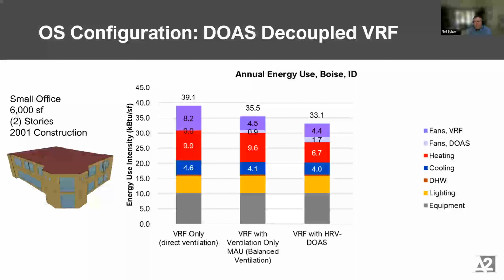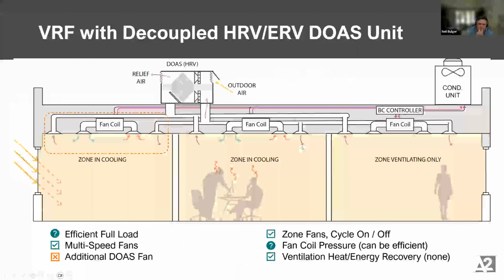But when we do that, we see the same step change, right? So we anticipate the fans are doing the same thing. They're still three-speed, multi-speed fans. So we get about the same. The DOAS now is doing more fan energy, has to push through the heat recovery device, but we make up for it in our heating savings.